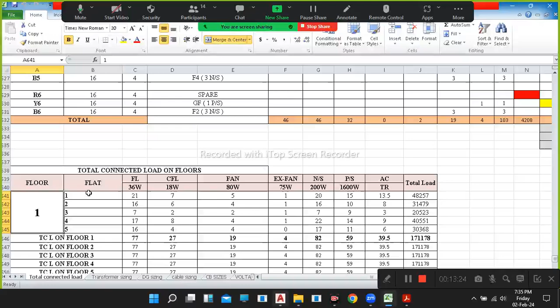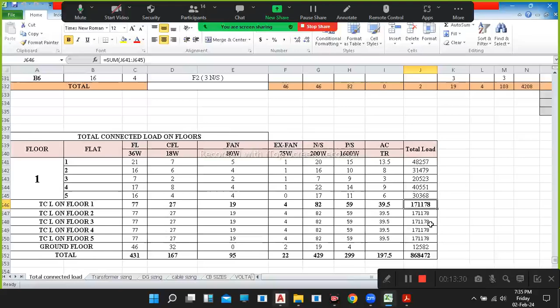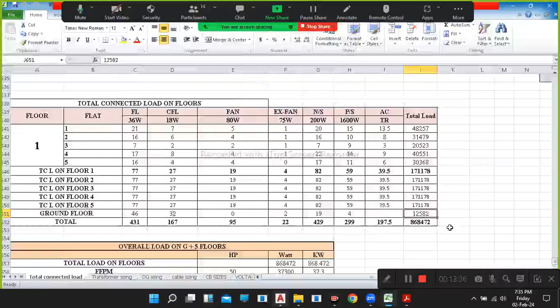Now in first floor there are 5 flats. Estimating the total load now. First floor 5 flats, each flat lights, fans, exhaust fan, total load. We got the total load. What is the total load on first floor? 171.178 kilowatt. Second floor is also the same. Third, because it's a typical layout, fourth, fifth, and ground floor 12582. When we added the total load, what is the total load? 868.472 kilowatt.